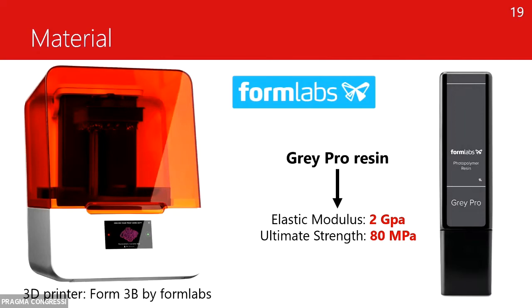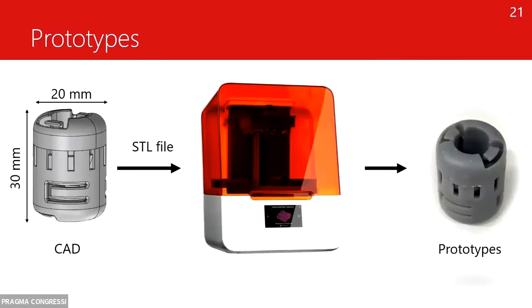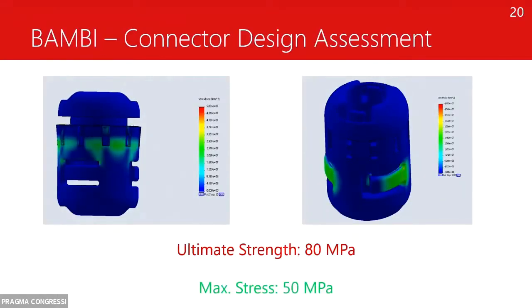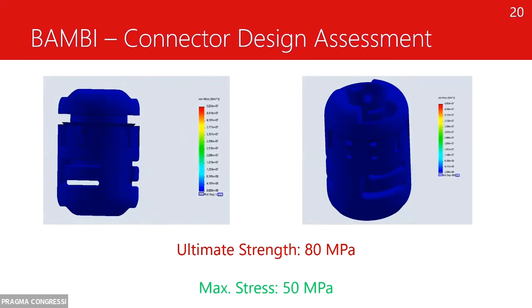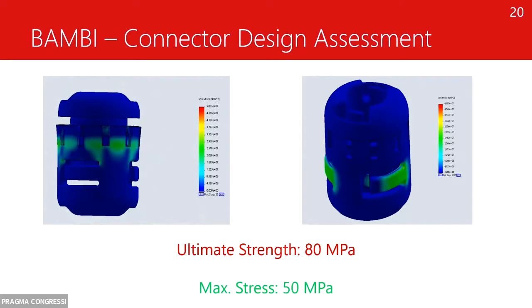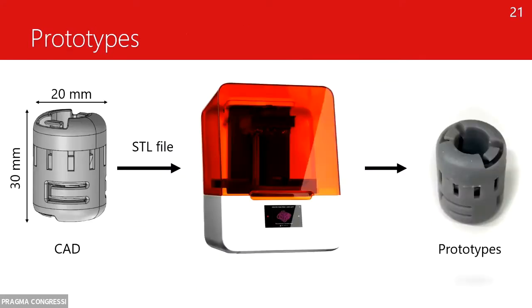And before starting with the prototyping, we performed some numerical simulations to understand if, during the assembling of the device and during the working phase of the device, the maximum stress is lower than the ultimate strength. And we had very good results because we are more or less at half of the ultimate strength. So from the CAD, we pass to the prototypes.